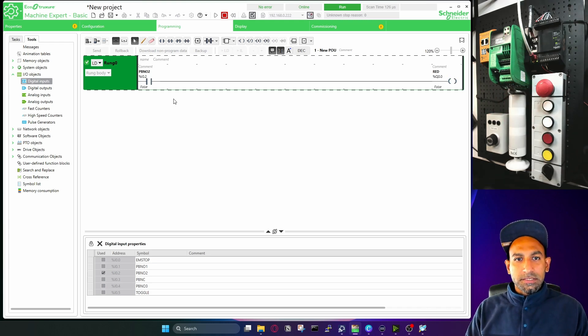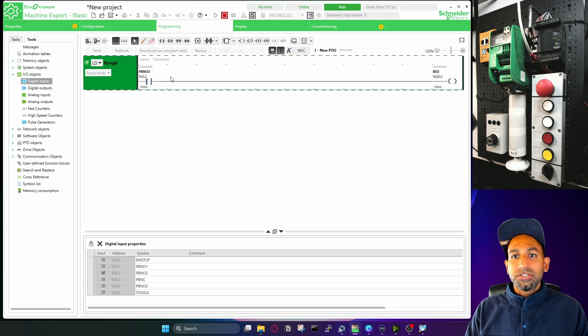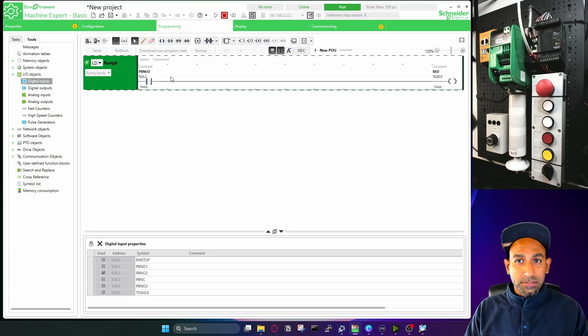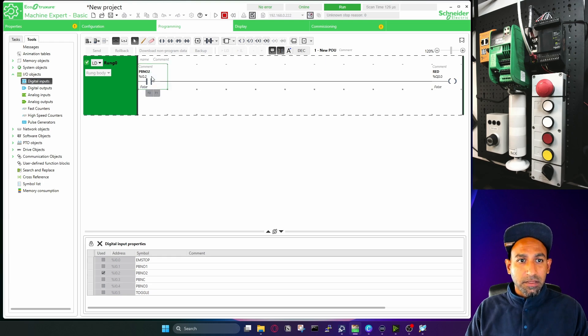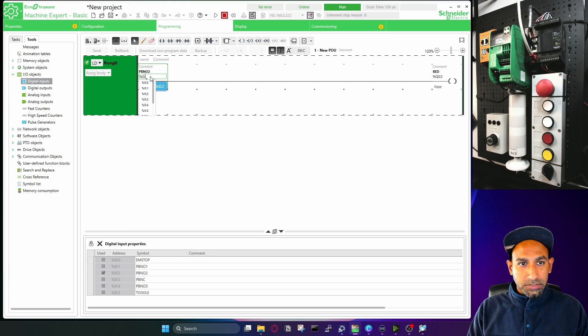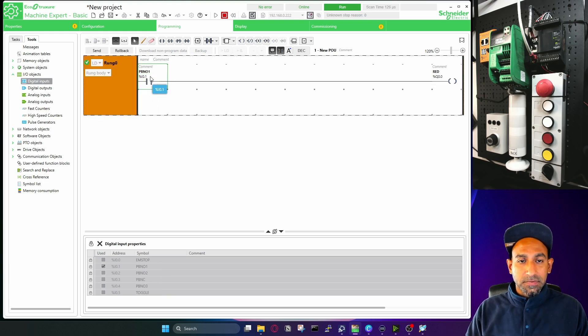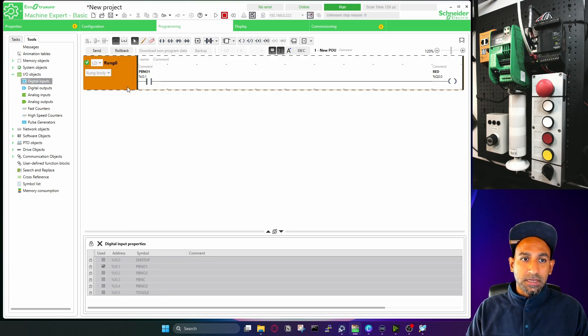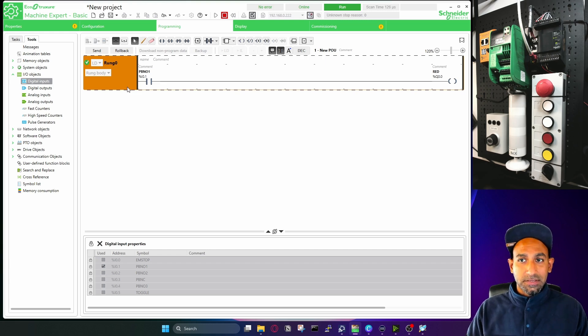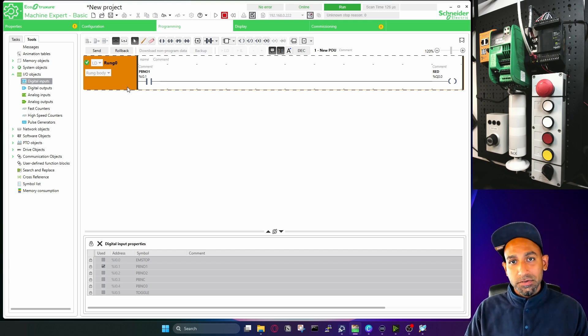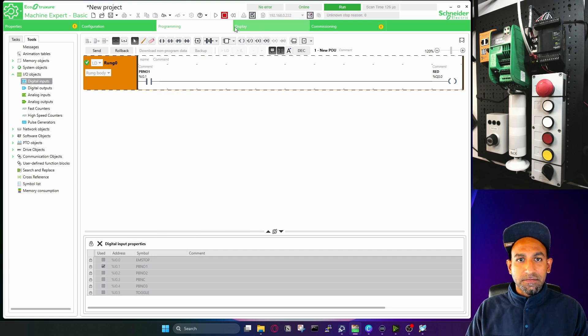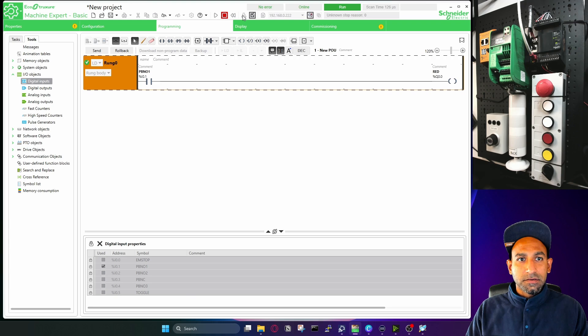So once it's downloaded, I can come back to programming again. And now I can go to run mode. So now it's I0.2. So it's my second input, which is actuating my output. Now, one more thing is, if I want to change, make the changes while PLC is in run mode, while PLC is online mode, I can do that as well. So in this case, I can double click here. And now I will change it back to one and press enter. In this case, you will see the color changes, the color indicates that you made some online changes, it has to be downloaded to the PLC.